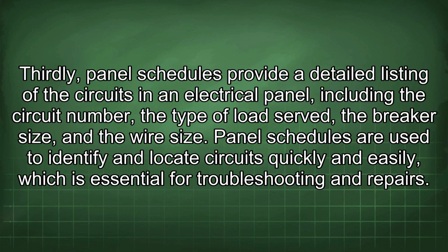Panel schedules provide a detailed listing of the circuits in an electrical panel, including the circuit number, the type of load served, the breaker size, and the wire size. Panel schedules are used to identify and locate circuits quickly and easily, which is essential for troubleshooting and repairs.